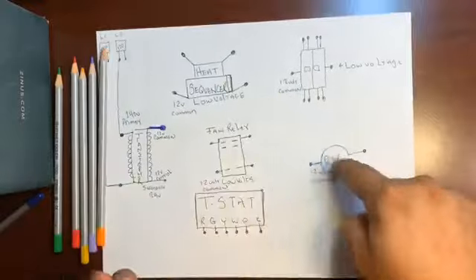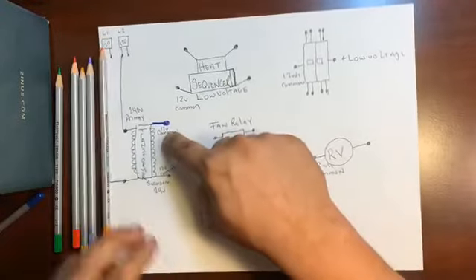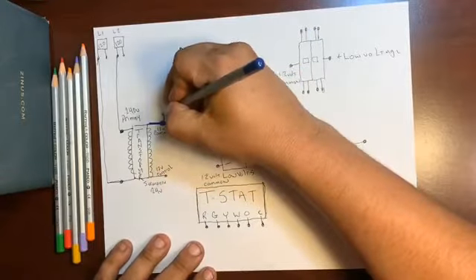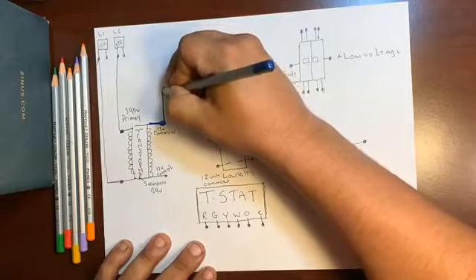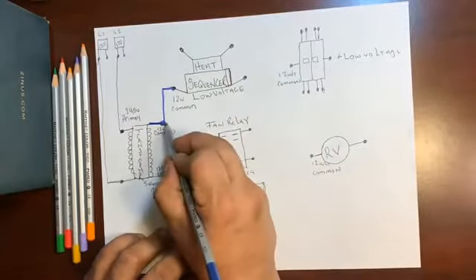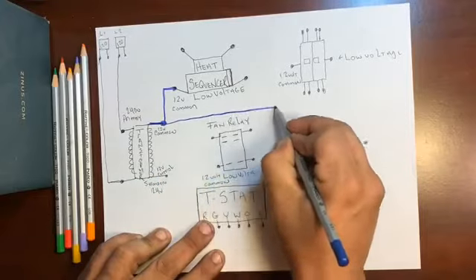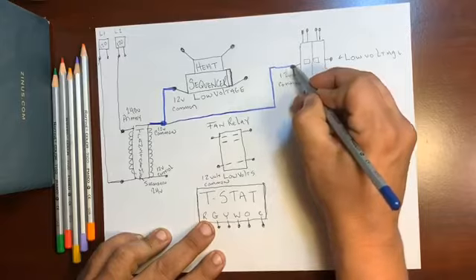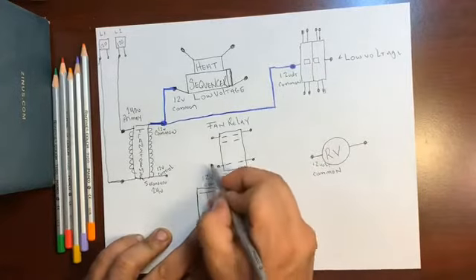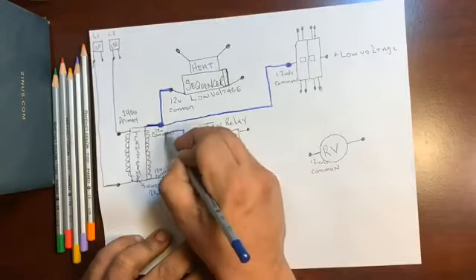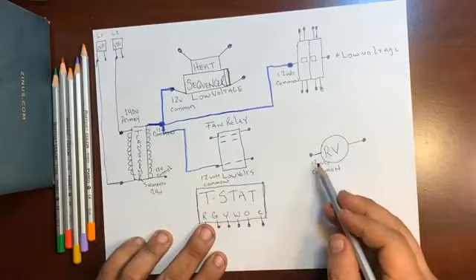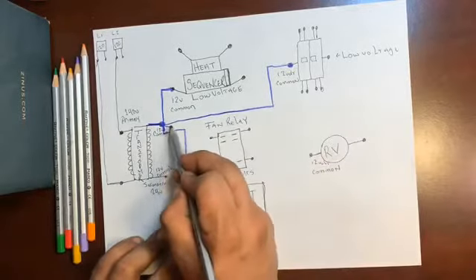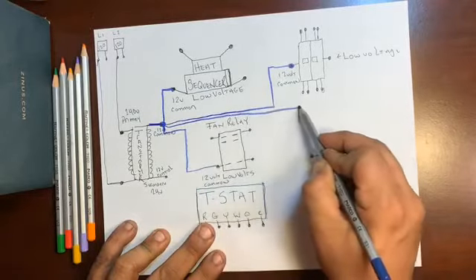So number 1 rule is put the common in my hand. Every single one of these relays demands 12 volt common from this transformer. So the first thing we're going to do is put the common in my hand. We take our blue, we're going to run 12 volts up to 12 volt common on the heat sequencer. We're going to take this common and run it to 12 volt common on the compressor contactor. We're going to take this fan relay, take our 12 volt common, and it also is going to go to 12 volt common blue. Reversing valve, no different. We're going to take this common down, bring another one out, and drop down to the 12 volt common leg.